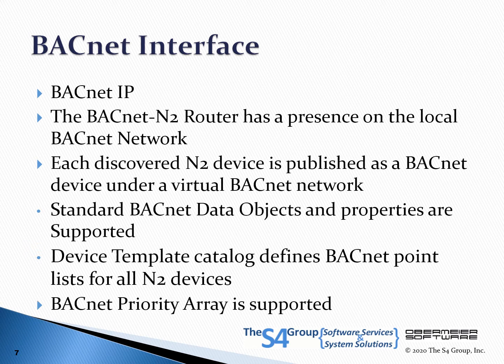Device IDs are based on the N2 address and user-specified offset. BACnet point properties are defined in the S4 device templates for each device and installed application. Points in template definitions are easily modified or pruned to create custom engineered solutions.